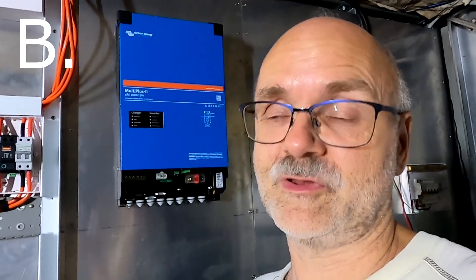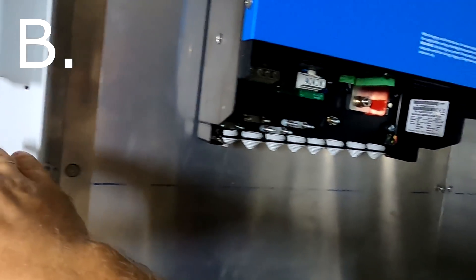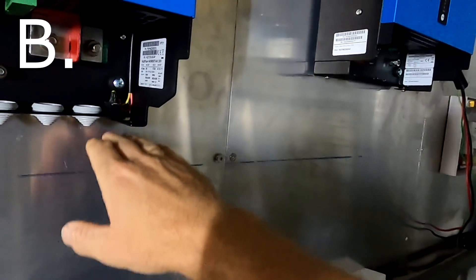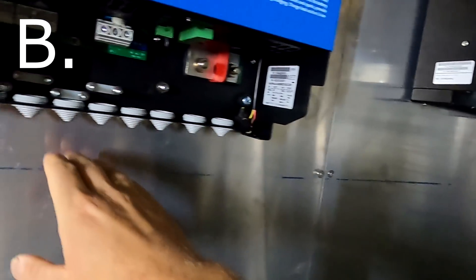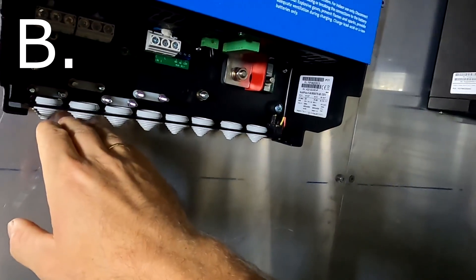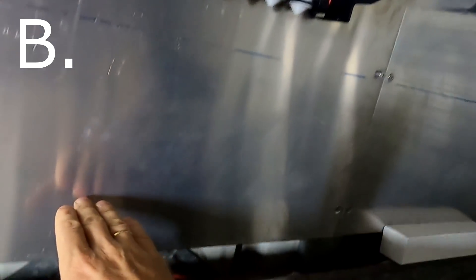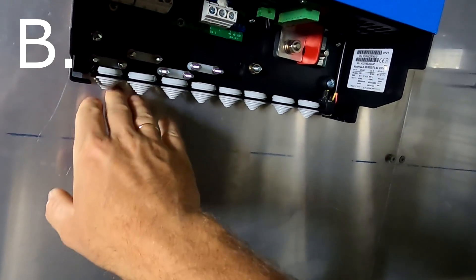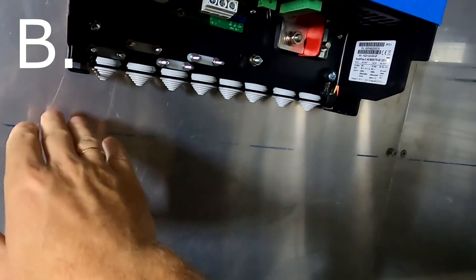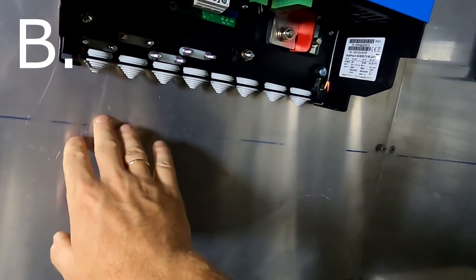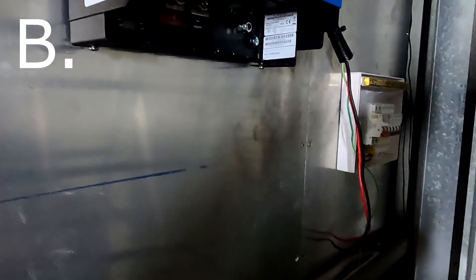I think it got around two or three votes if I can remember correctly. Solution B was, well, we don't give a shit. We will have crossings. We just pull our DC across here into the inverter and the AC is coming out here going all the way down into the tray and we'll have a crossing from AC and DC over here and the same with this inverter somewhere over here. Another 90 degree crossing. No parallel cables in one duct, just a 90 degree crossing would be another solution, right?